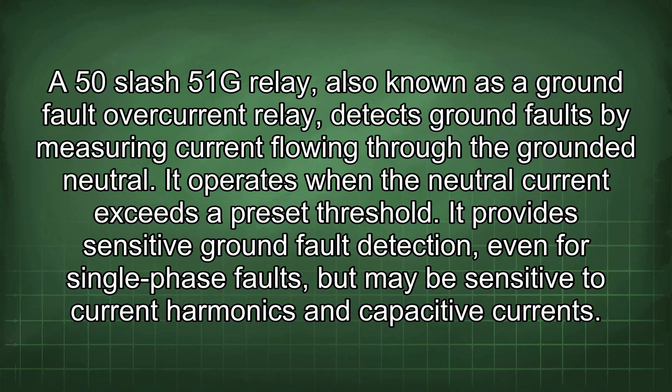A 50-51G relay, also known as a ground fault overcurrent relay, detects ground faults by measuring current flowing through the grounded neutral. It operates when the neutral current exceeds a preset threshold. It provides sensitive ground fault detection, even for single-phase faults, but may be sensitive to current harmonics and capacitive currents.